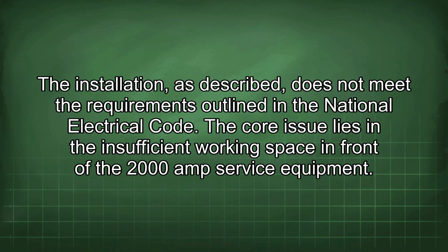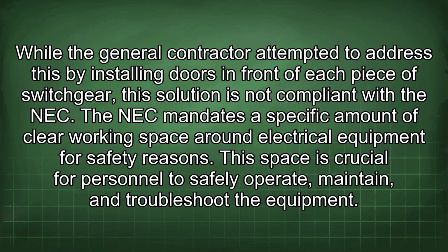The installation, as described, does not meet the requirements outlined in the National Electrical Code. The core issue lies in the insufficient working space in front of the 2000 amp service equipment. While the general contractor attempted to address this by installing doors in front of each piece of switchgear, this solution is not compliant with the NEC.